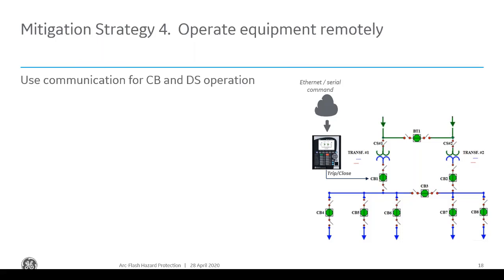Obviously, with modern microprocessor relays, if you have communication, serial or Ethernet, and if you saw the webinar last week, we talked a lot about the advantages of Ethernet over serial, you can basically operate the equipment remotely and not have to be in front of it to be exposed to the hazard. And once it's de-energized, you can then have carte blanche to go and work on the piece of equipment.